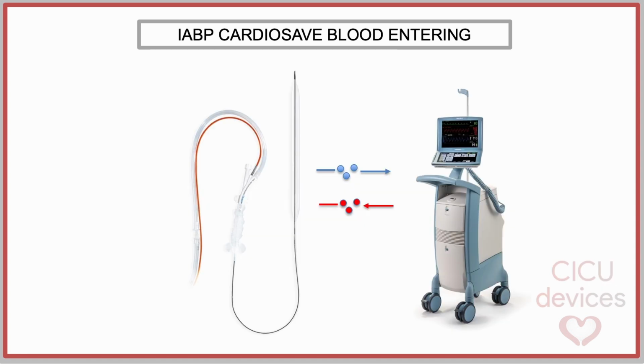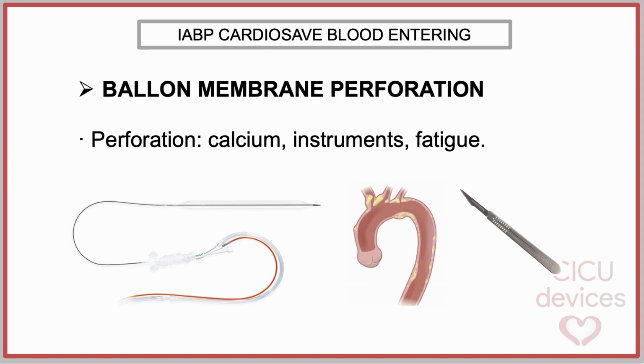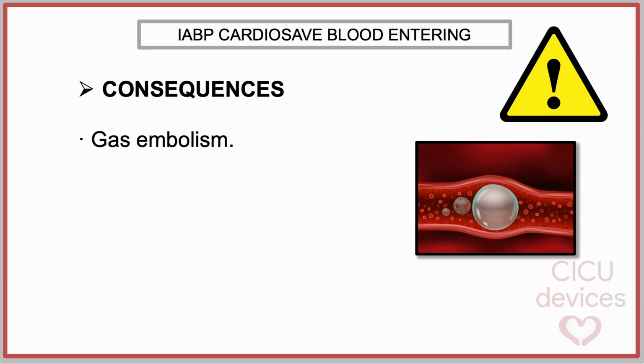The root cause was determined to be blood entering the console through the extender tubing when therapy continued with a perforated balloon that was not detected promptly by the user or the system. Balloon membrane perforation may result from mechanical contact with calcified aortic plaques, sharp instruments, or material fatigue. This event may lead to the following clinical consequences: a leakage of helium from the catheter into the patient's bloodstream, which may result in gas embolism, posing a serious clinical risk.